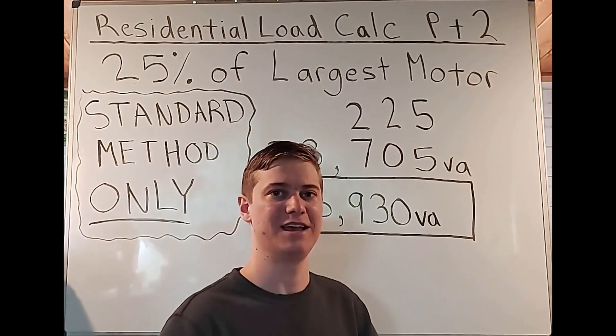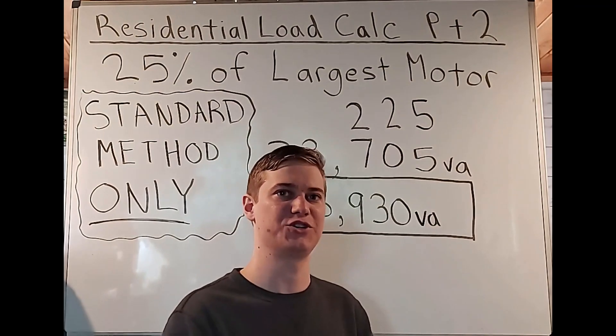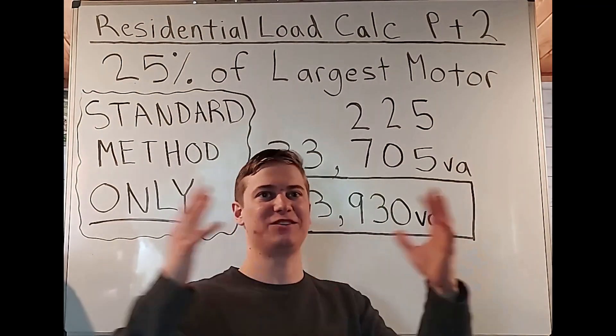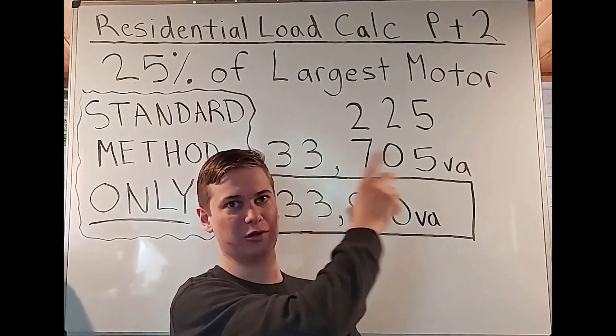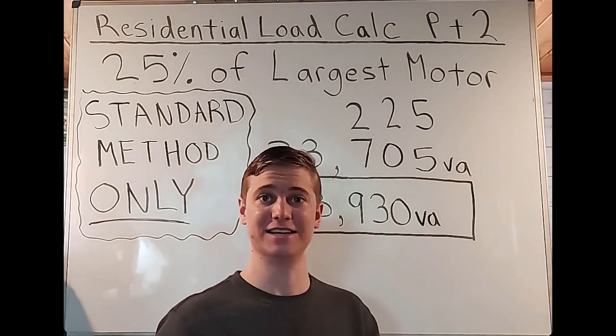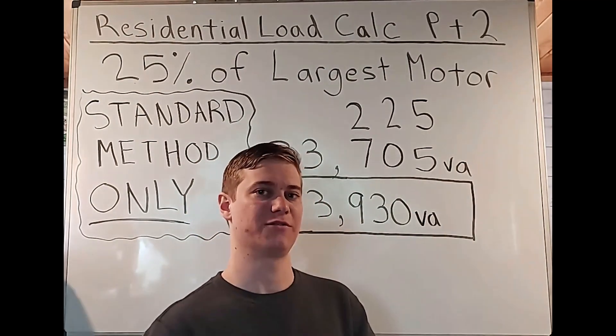So 25% of it, that number, like I showed you, is going to get added on the total load that we calculated other than that one final calculation. So that's why I do it at the very end. And you're going to see in my next videos, I'll just show you that I basically get the total load for the house. And then I add the 25% of the largest motor. And that is the entire demanded load for that house.